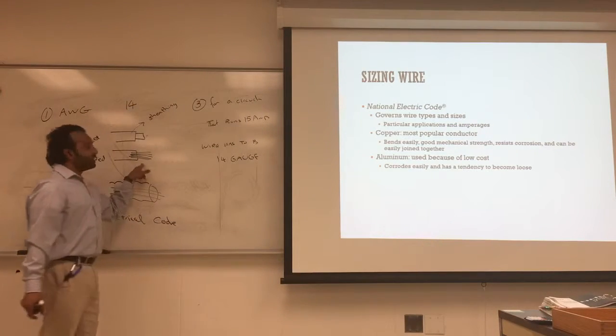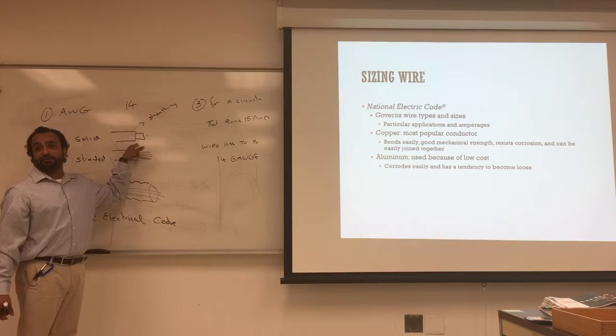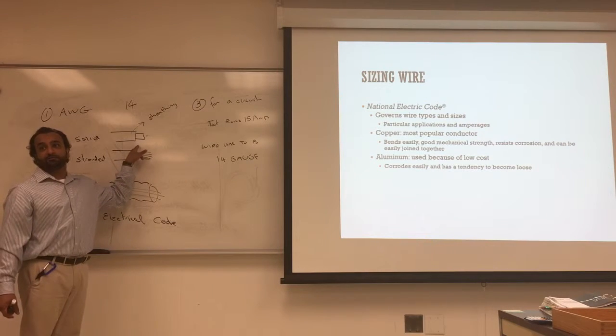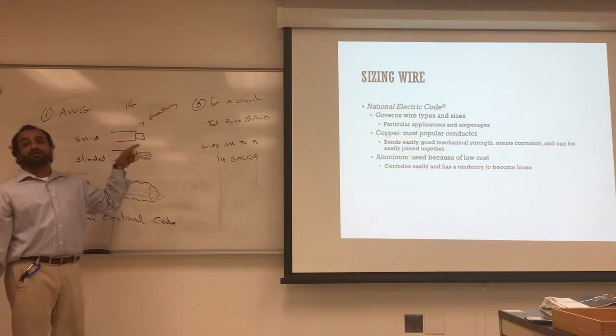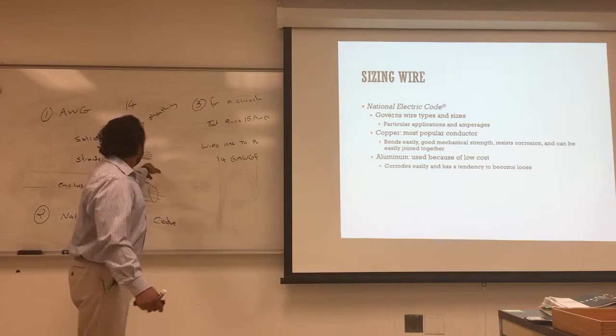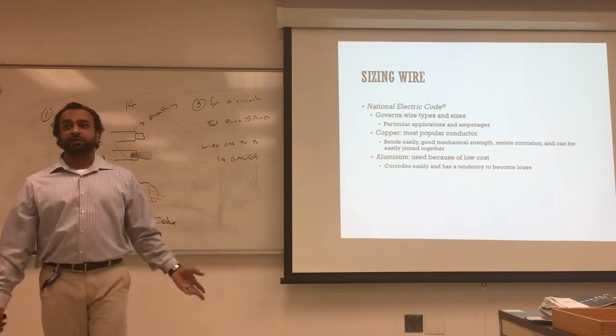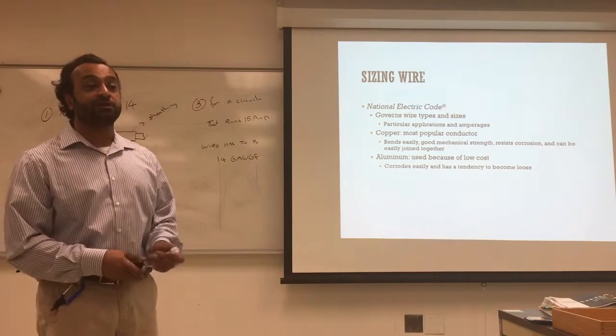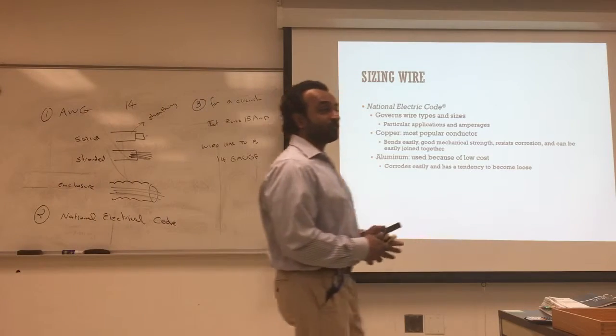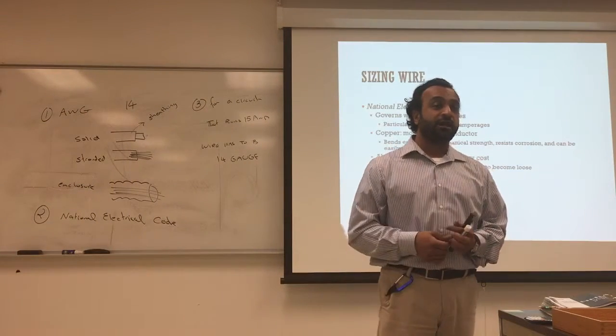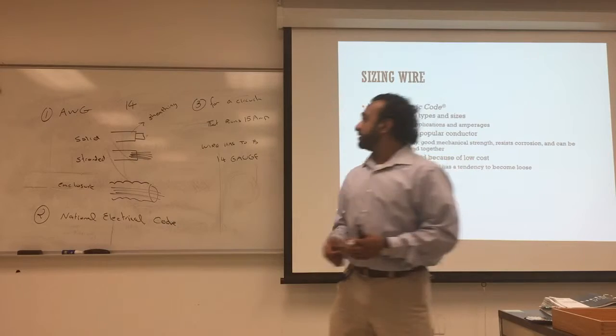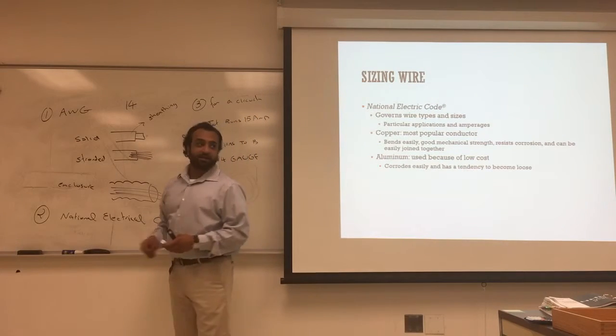The code says you're not supposed to connect stranded and solid wire together in a wire nut. That's debatable—people still do it. But you're not supposed to, because the connection will be different. Why do we use solid and why do we use stranded? They have different applications, and you'll see why. When you connect on a board using solid instead of stranded, you don't get the same connection.